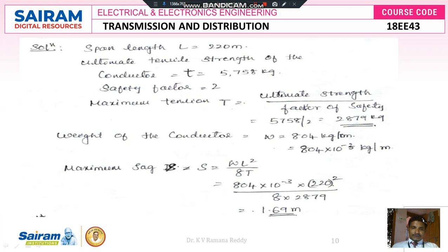Weight of the conductor w = 804 kg per kilometer = 804 × 10⁻³ kg per meter. Now the maximum sag formula: S = wL²/8T = (804 × 10⁻³ × 220²) / (8 × 2879). Doing the simplification, the maximum sag S = 1.69 meters.